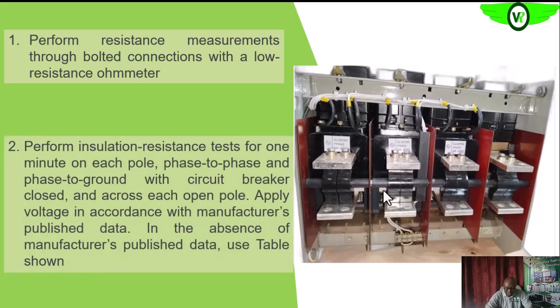Then insulation resistance, we can also perform with the megohmmeter. After doing the appropriate range selection on the selection switch, we test the insulation between phases: between line 1 and line 2, line 1 and line 3, line 2 and line 3, line 1 neutral, line 2 neutral, line 3 neutral. And then each of these to ground. We want to check that we have the appropriate insulation, and that it meets what is required in our facility.